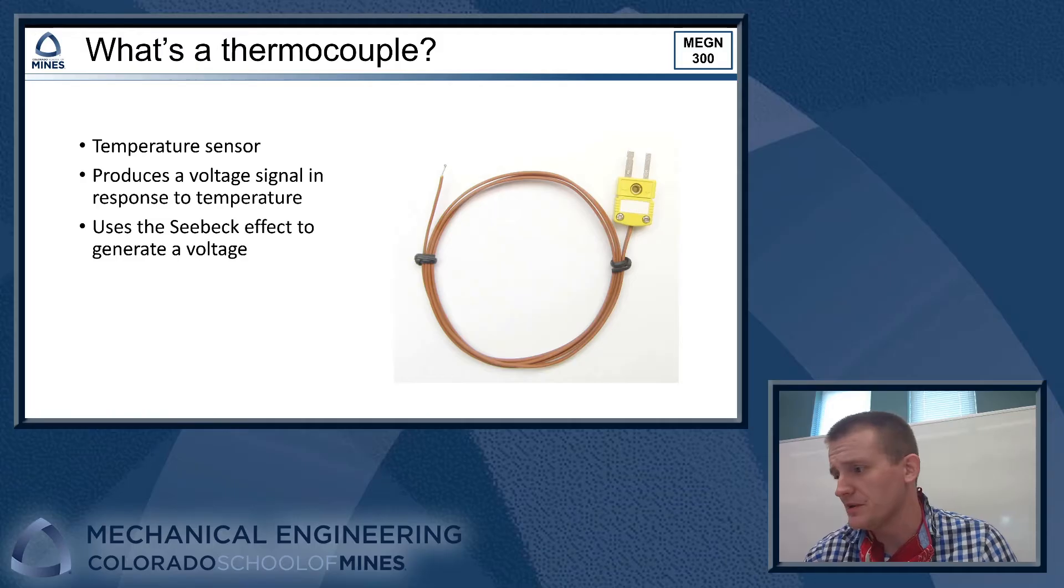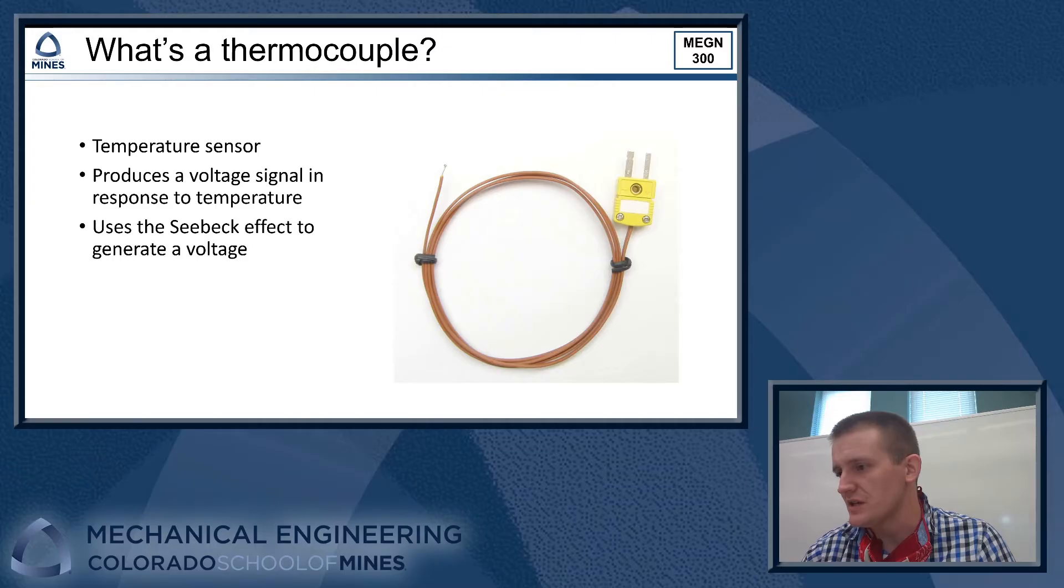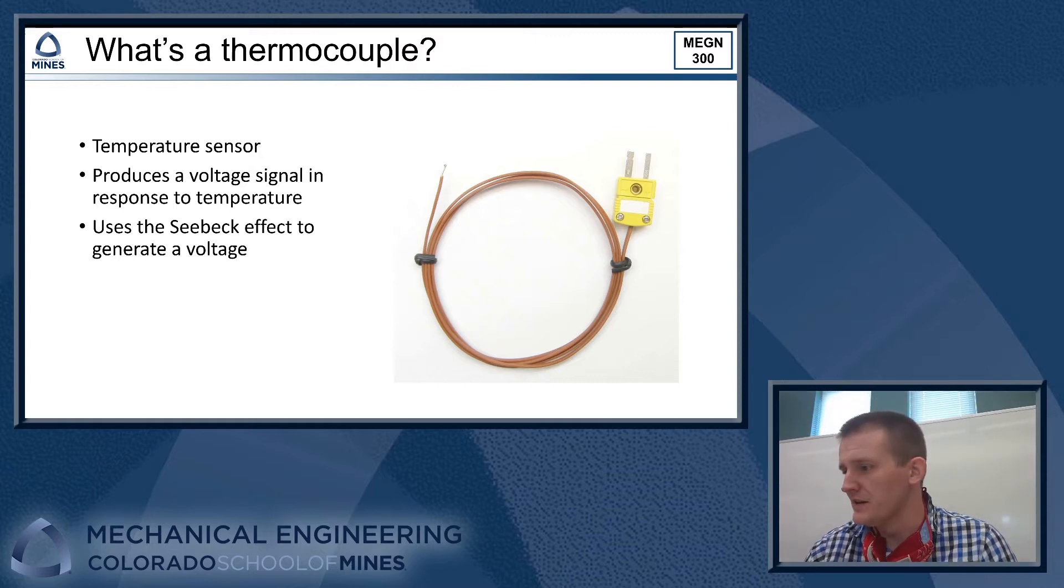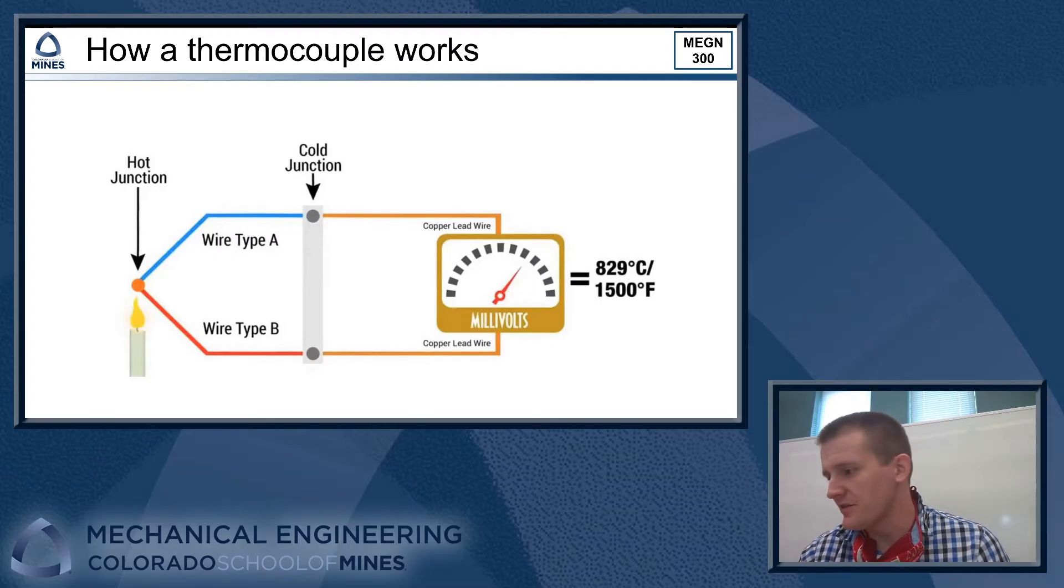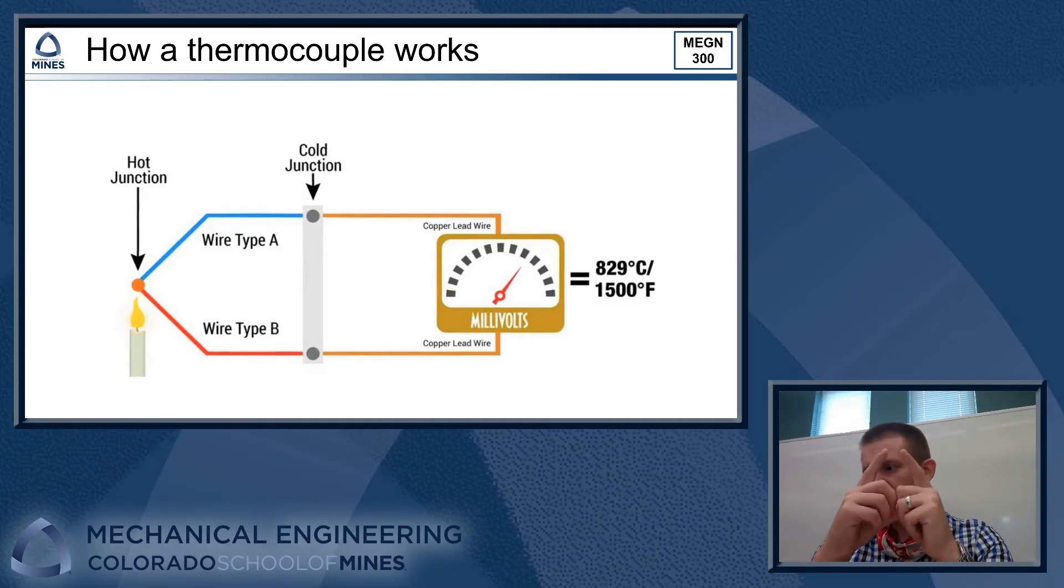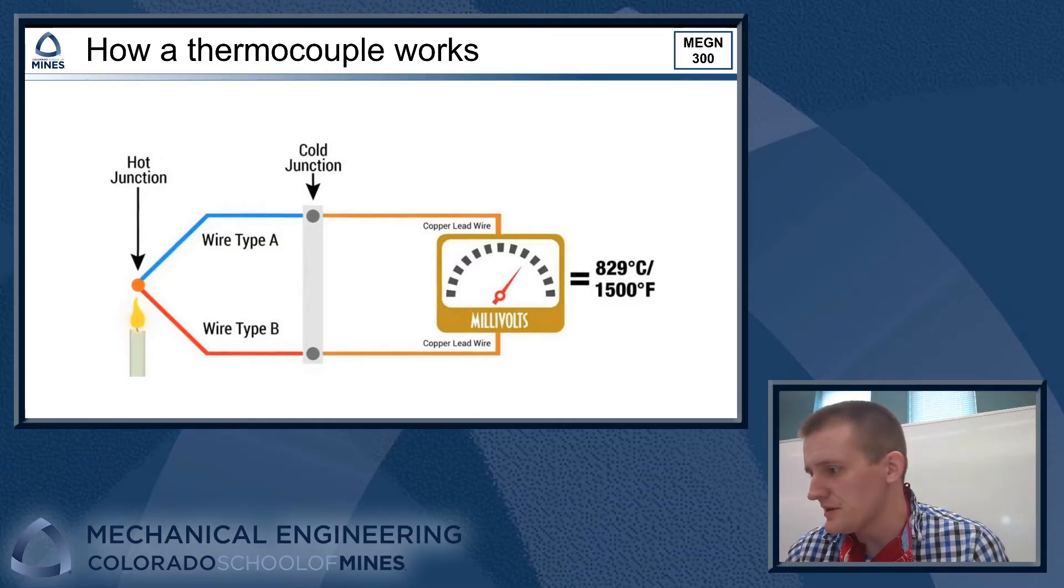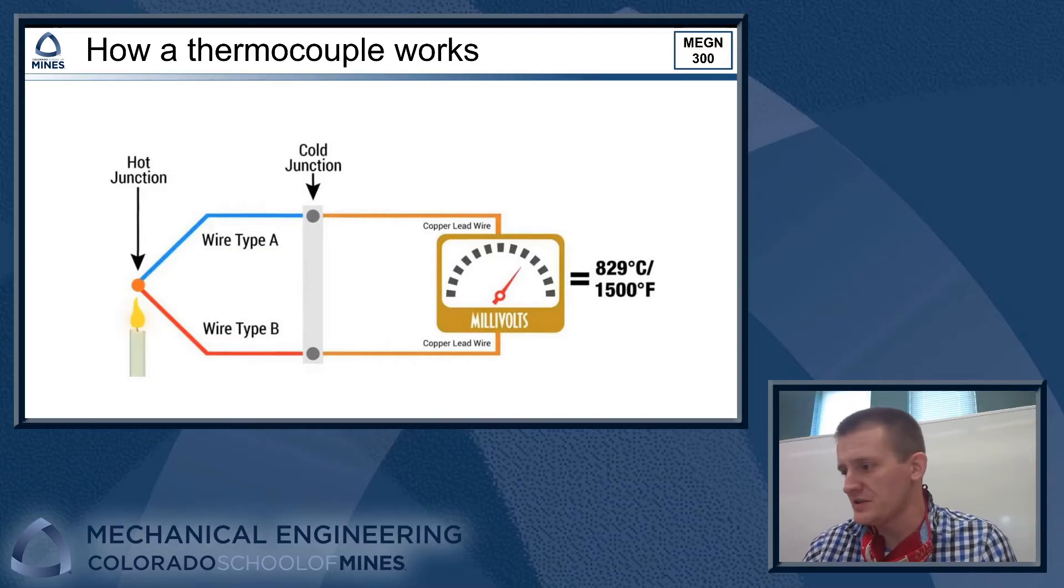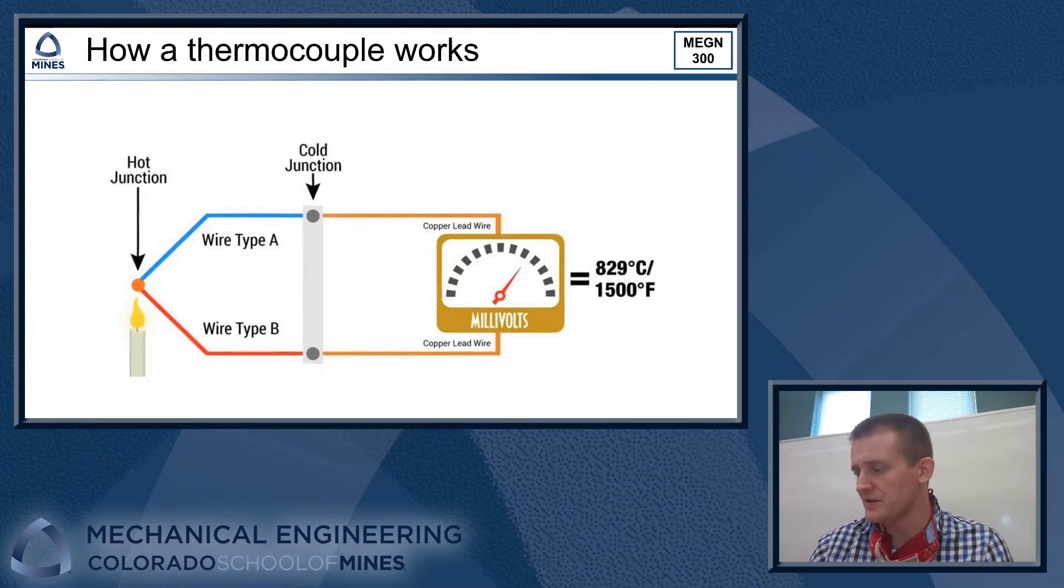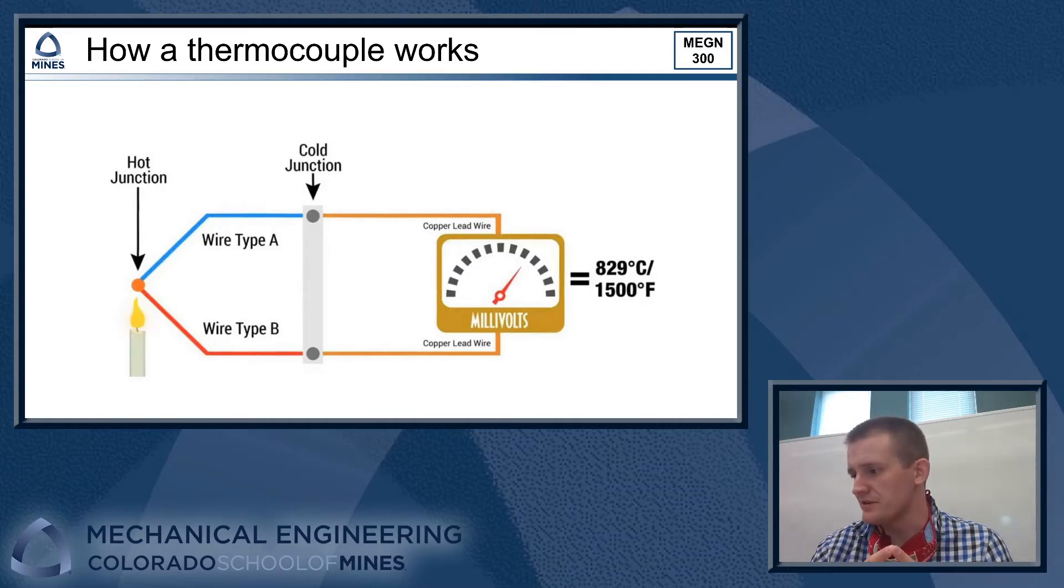First of all, we should talk about what is a thermocouple. It is a type of temperature sensor and it produces a voltage signal in response to temperature. It does this by using something called the Seebeck effect, which will generate a voltage when you expose these wires to different temperatures. Inside of the thermocouple are two wires which are made of different alloys. Those wires are typically taken together and they're actually welded at the tip of the thermocouple where the temperature measurement actually happens. When we expose those wires to a temperature, we have a temperature difference across this system of the wires where we've got the two alloys welded together. We get a voltage potential that's generated by those two different alloys being in close contact with one another.